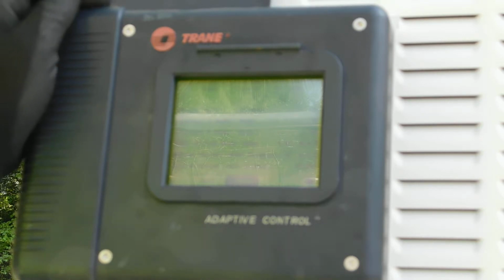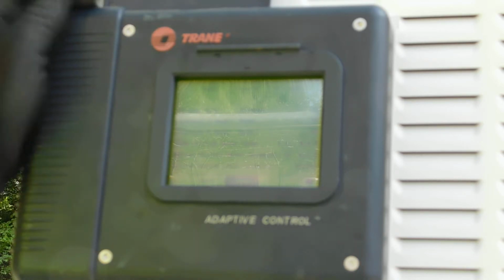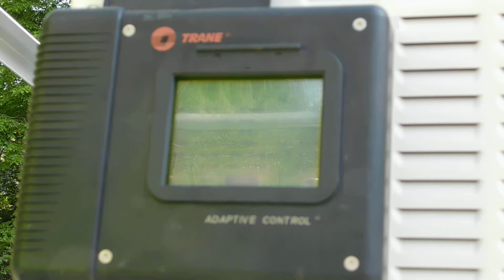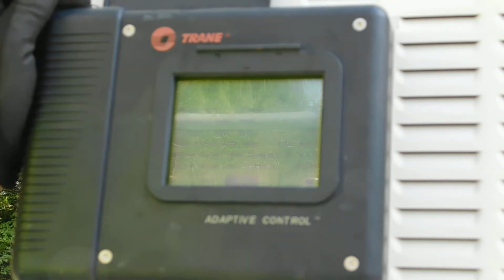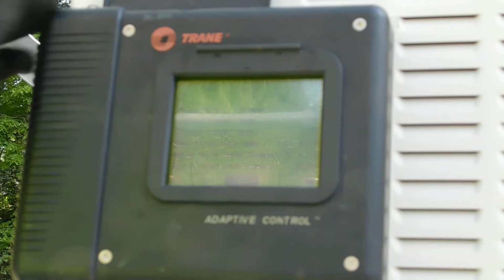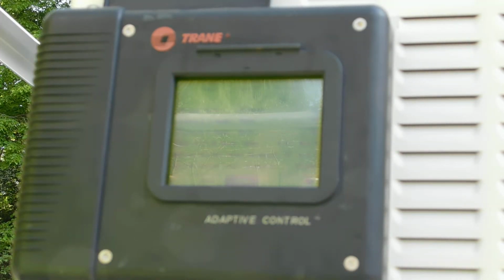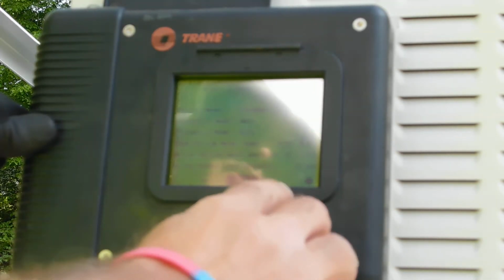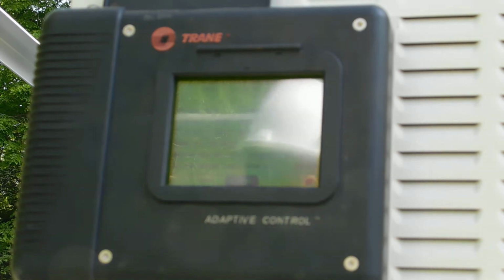Yeah. The set point, is that controlled locally, or is that controlled via the BMS? That can be set in here to be front panel or by the BMS. So I'm assuming you'll be doing it by the BMS. Right. If the BMS went wrong, there's a feature in here where we can set it to local control. Local control, yeah. So if you had a problem with the BMS, we just go into here and set it for local control. So there is that facility if you need to, but you're going to be doing it from the BMS. So if you watch this area here now, you'll see a tab come up which will say alarm, and I'll show you once I've pulled the...